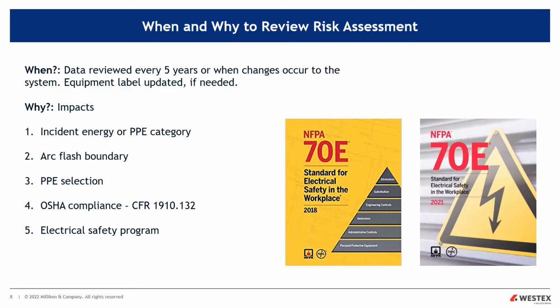And that can affect other personnel, especially in a task-based program where the supervisor is not wearing PPE because they think they're outside the boundary. Well, if that boundary has changed and they don't know it, they may be in the boundary and they may be at risk. Of course, it affects your PPE selection, making sure you have the right PPE with the arc rating. It may also change your program. Are you in a task-based program because you don't have a lot of exposure, but maybe when you relook at the risk assessment, you have more exposure on more equipment, you may want to go with a daily flame-resistant arc-rated daily wear program. And of course, for OSHA compliance, the big one is Code of Federal Regulations 1910.132, which is hazard assessment and equipment selection, right?